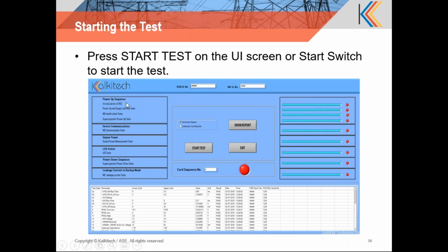We have a power up sequence consisting of tests like device communication, meter output power (RF power measurement), and LED status test. Power up is followed by a power down sequence and leakage current test. For each test, a progress bar displays the status, along with the overall result of each test and the final result.